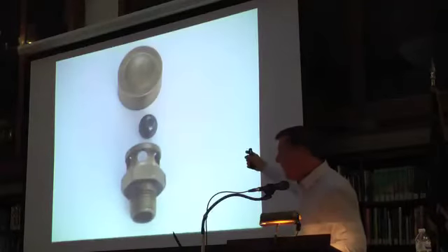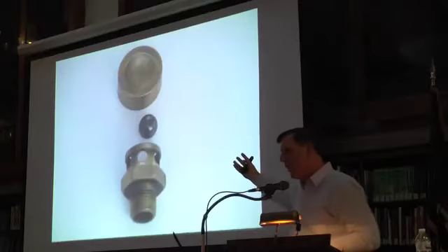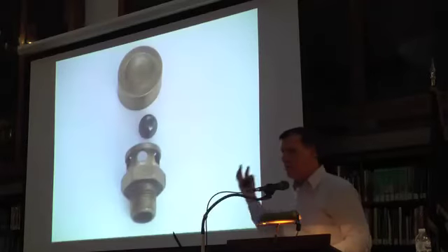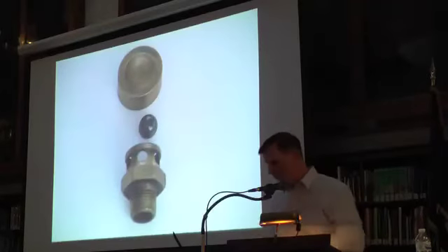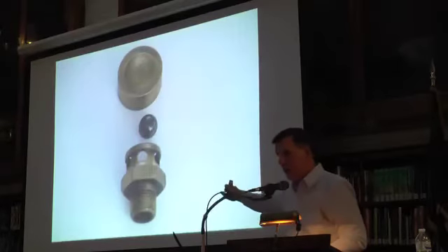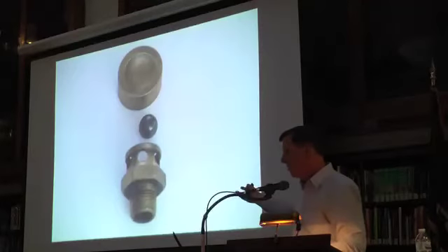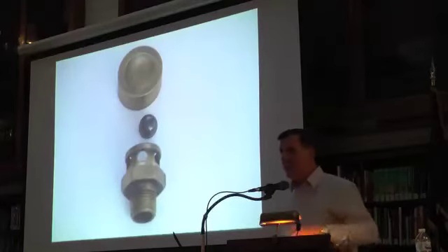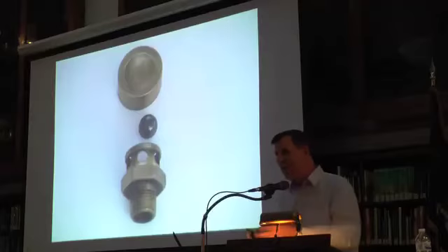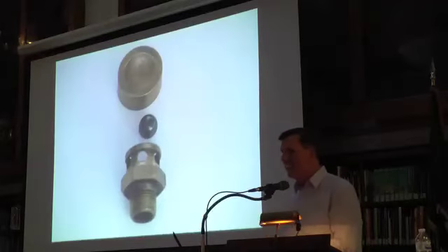So walk in there and you find out somebody might have taken that thing out because they raised the pressure too high and it was blowing steam out of there, or traps in the building may have gone bad and the steam is blowing into the returns and blowing out of that little hole. So some knucklehead will go in and take that thing out and replace it with a pipe plug, because pipe plugs are cheaper than air vents. And at that point, the laws of economics override the laws of physics, and now you have a building that won't heat because somebody went in there and took the air vent out and put in a plug. See?